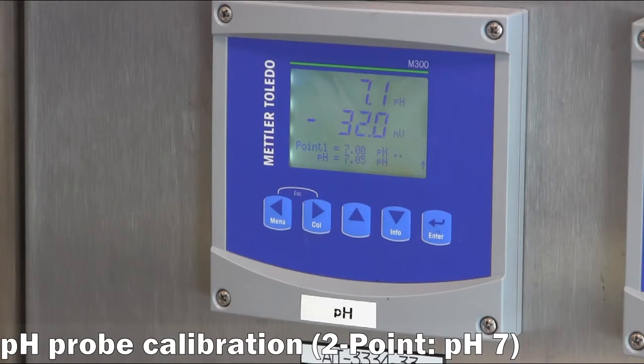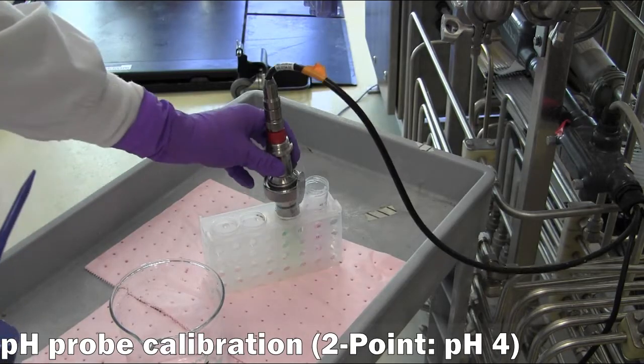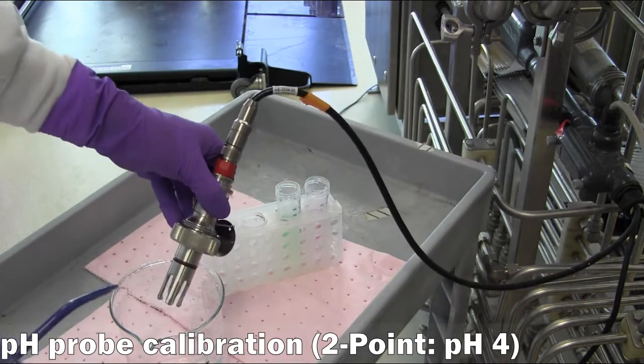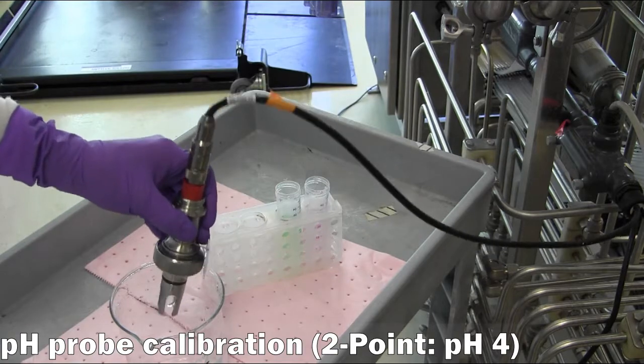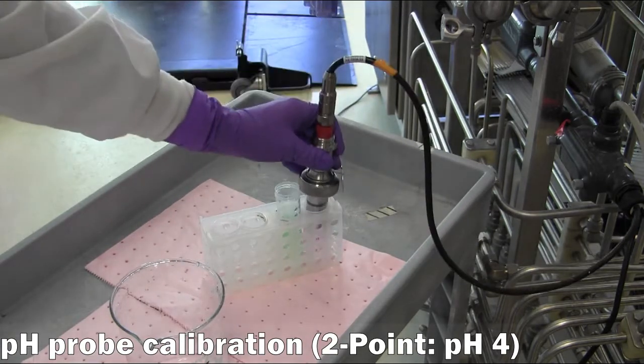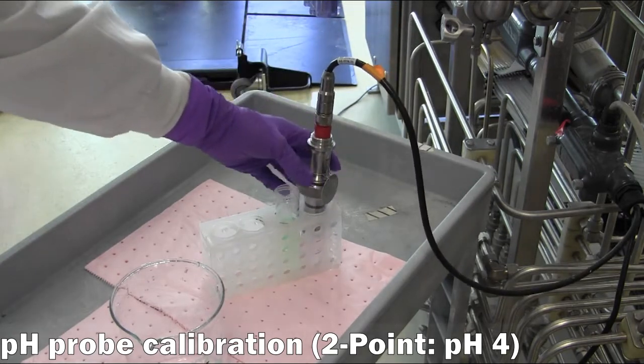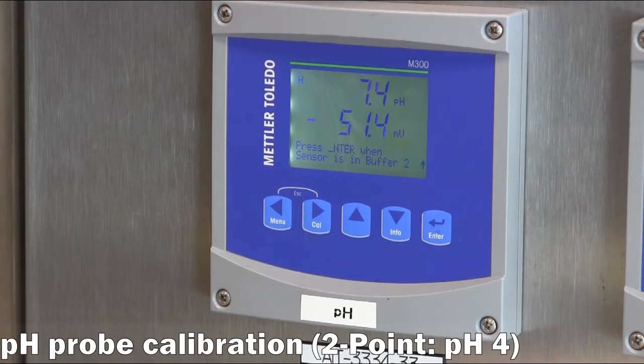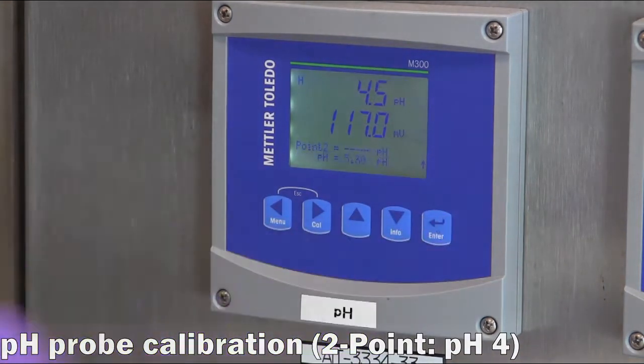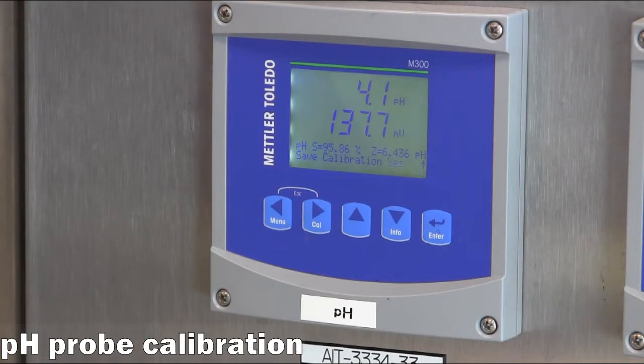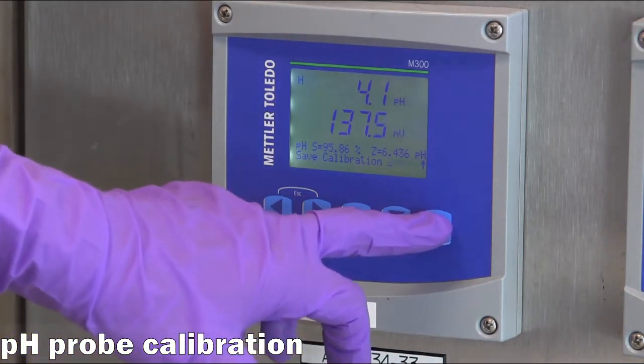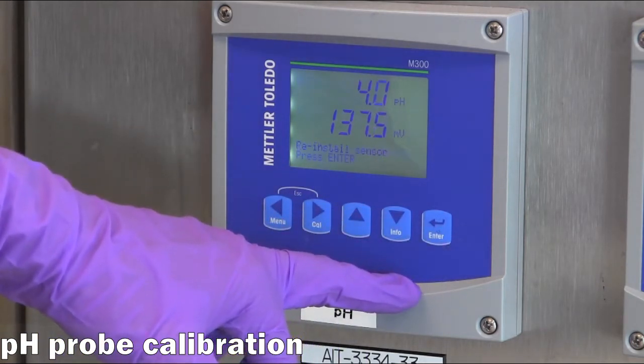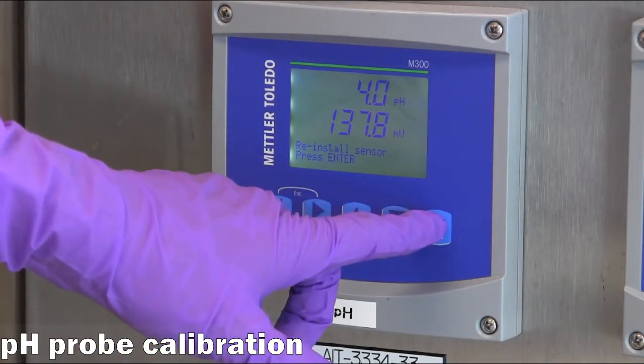Press enter. Once the signal stabilizes, the transmitter will automatically display a prompt to place the probe in the second buffer. Remove the probe, rinse with DI water, dry, and place the probe in the second buffer. Press enter. Once the reading stabilizes, the display will automatically show the slope calibration factor S and offset calibration factor Z. Select Yes to save calibration. And press enter.